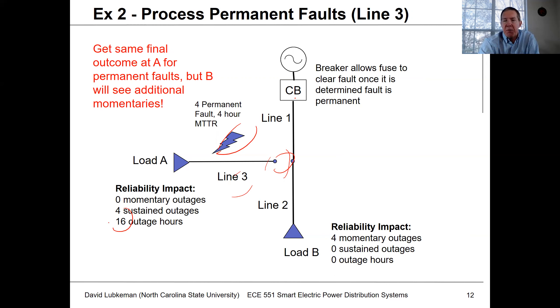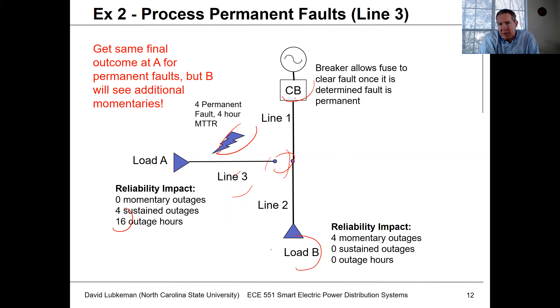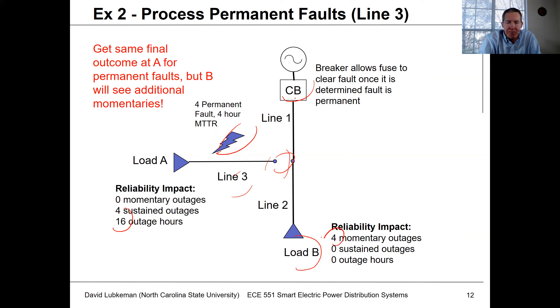Because the circuit breaker is set up for fuse savings, it tries to clear the fault first — meaning customers at load B see blinks and momentaries. So load B sees four momentary outages associated with those four faults on line section three. The trade-off is: to get less fuse blowing, we have to live with more momentary blinks.